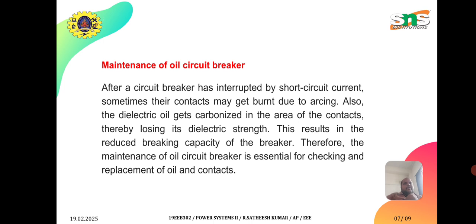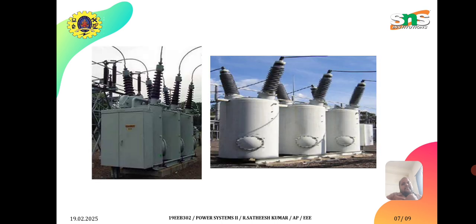Maintenance. After the air circuit breaker, this oil circuit breaker has interrupted the short circuit current. Sometimes the contacts may get burned due to the arcing. Also, the dielectric oil gets carbonized in the area of the contacts, thereby losing its dielectric strength. This results in reducing the breaking capacity of the breaker. Therefore, maintenance of the oil circuit breaker is essential for checking and replacement of the oil and contacts.